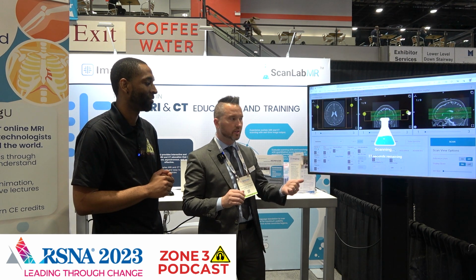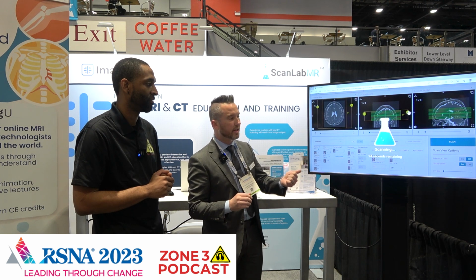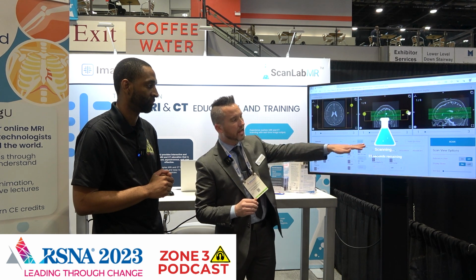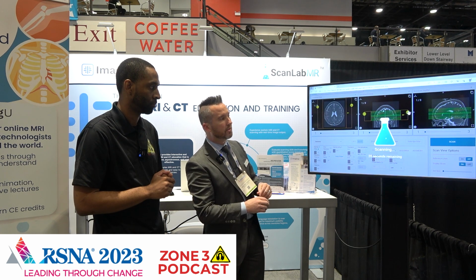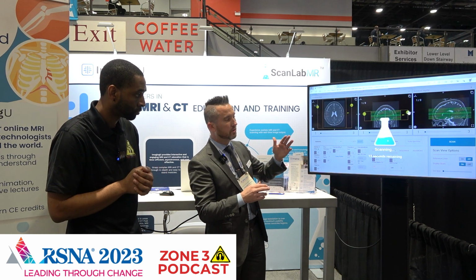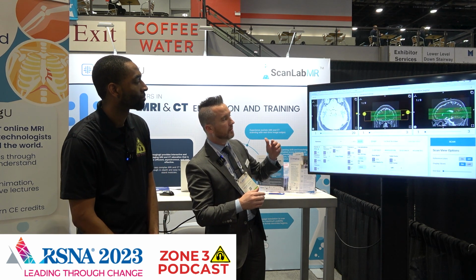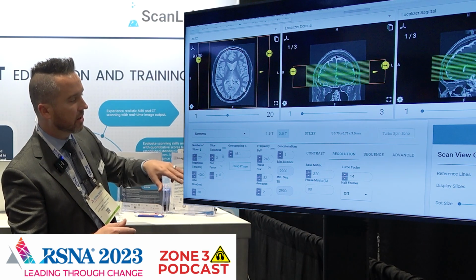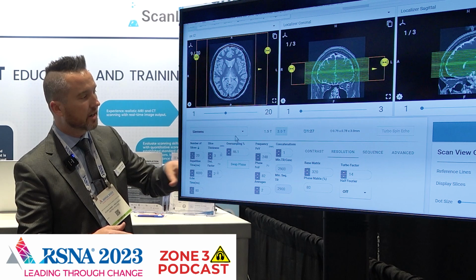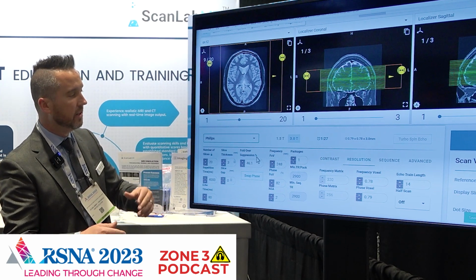So from an educational standpoint, we're excited about this to be able to simulate. This is something that would normally take a minute and a half with every parameter that we've got, but we do it in about 14 seconds. And this is real-time stuff. Typically, internet connection-wise, it can be anywhere between 8 to 17 seconds. So at this point, you can see exactly at 3 Tesla what a TE of 80, a TR of 4,000 milliseconds, and an echo train length, or turbo factor, of 14 looks like. Wow. You can see that across vendors.